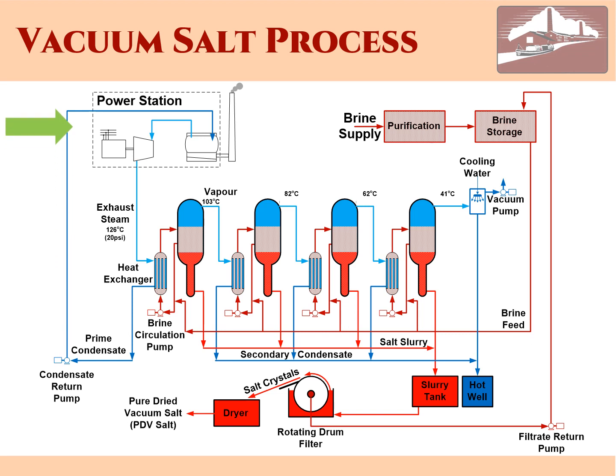To complete the picture, we must add the powerhouse, which supplies the steam. Condensate from the first effect is returned to the boiler feed system for reuse. Brine is fed from the brine holding tank to maintain liquid levels in the effects. The salt slurry is drained off and collected in a holding tank, from where it is passed through a drum filter. As brine is pumped from inside the drum, the salt crystals are retained on the outside, from where they are removed by a scraper. The brine is returned to the brine tank for reuse.